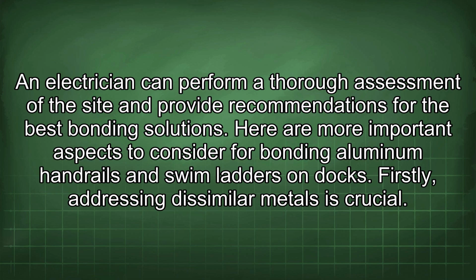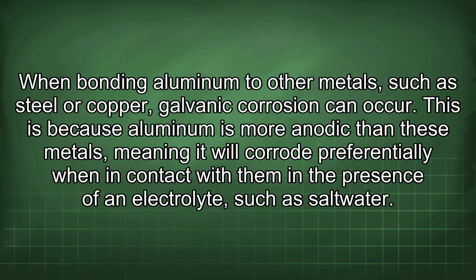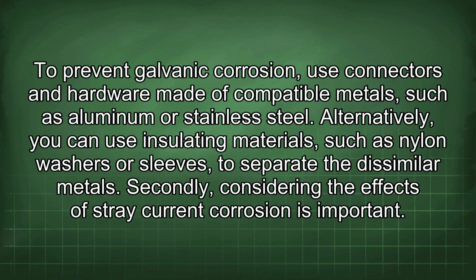Firstly, addressing dissimilar metals is crucial. When bonding aluminum to other metals, such as steel or copper, galvanic corrosion can occur. This is because aluminum is more anodic than these metals, meaning it will corrode preferentially when in contact with them in the presence of an electrolyte such as salt water. To prevent galvanic corrosion, use connectors and hardware made of compatible metals such as aluminum or stainless steel. Alternatively, you can use insulating materials such as nylon washers or sleeves to separate the dissimilar metals.